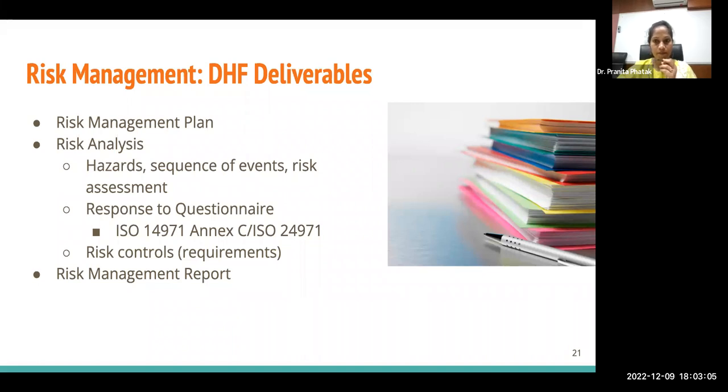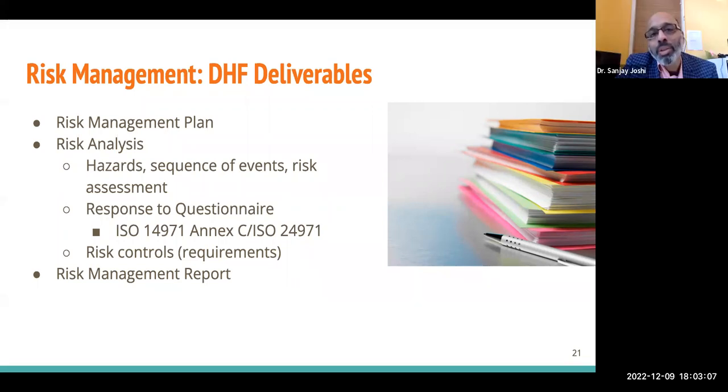Which risk class? Right. So that's a question that's not actually in scope of risk management. It's the medical device classification. And usually what you need is somebody who is well experienced in regulatory affairs. So either if you have your own regulatory affairs department, they can make a recommendation. You can also go to a regulatory affairs consultant and get a recommendation. And usually when you submit for clearance or approval to the government, you have to say what classification you are seeking. I would highly recommend going to a regulatory affairs person.